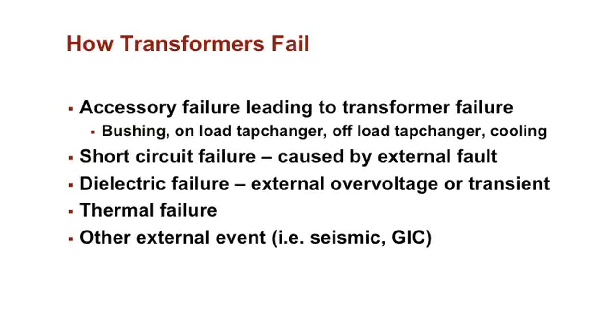Dielectric failure: there's some kind of overvoltage or transient voltage on the system, and again that comes back to the transformer, and it's more than the transformer can sustain. You could have a thermal failure. Now generally, thermal is something that happens over time, and it doesn't necessarily fail a transformer, but it gets to a point where the transformer has to be removed from service because it's gassing so much, or the cellulose has reached its end of life. And then there are other events that are more regional, such as earthquake, seismic, or GIC. So I'm going to go through all of these.